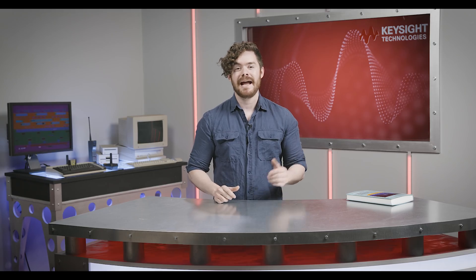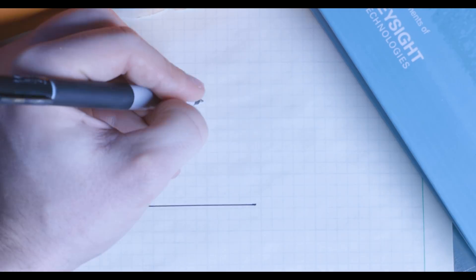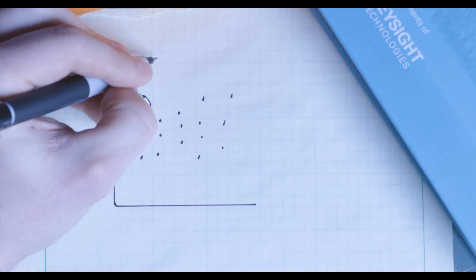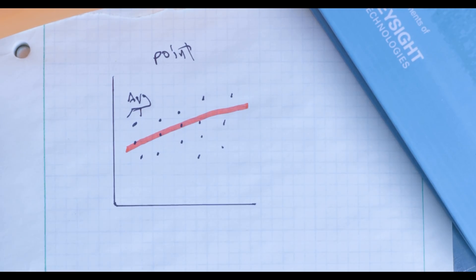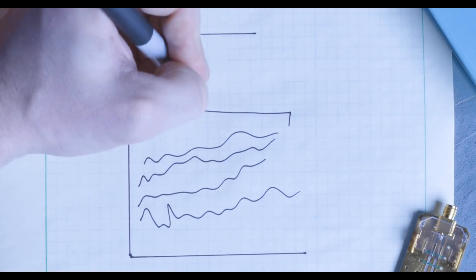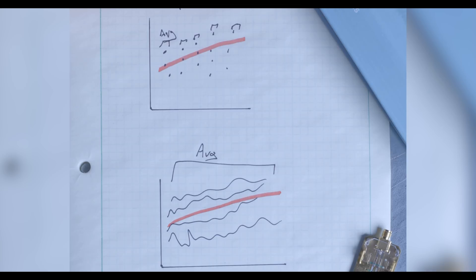Finally, you can use averaging to reduce noise. There are two types of averaging: point and sweep. Point averaging grabs each point a specified number of times and then moves to the next point. Sweep averaging takes a specified number of sweeps and averages the traces. Both give you the average of multiple measurements, which reduces the effects of random noise.